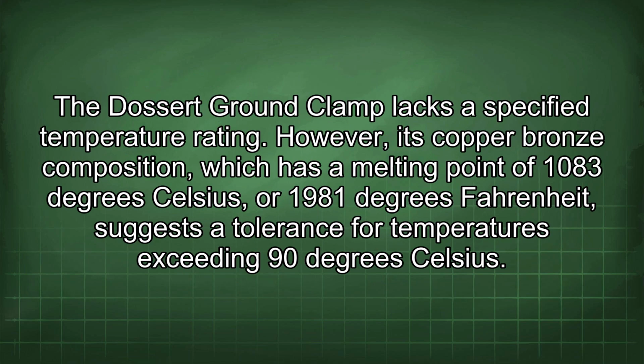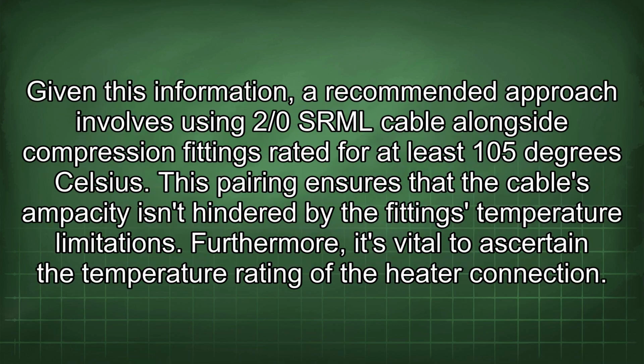The Dossert ground clamp lacks a specified temperature rating. However, its copper-bronze composition, which has a melting point of 1083 degrees Celsius, or 1981 degrees Fahrenheit, suggests a tolerance for temperatures exceeding 90 degrees Celsius. Given this information, a recommended approach involves using 2/0 SRML cable alongside compression fittings rated for at least 105 degrees Celsius. This pairing ensures that the cable's ampacity isn't hindered by the fitting's temperature limitations.